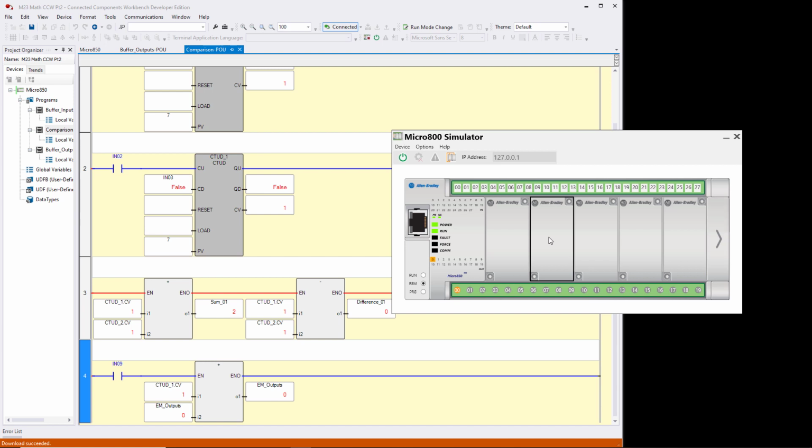But watch what happens as fast as I can turn it on and off. As fast as I could click it, it incremented to 291. So that means 291 program scans passed between when I clicked input 9 on and when I turned it off. So I'm going to double click it really fast. I'm not going to wait for it to turn on so that I can see it light up, just bang bang. Okay. Well, now we went up to 465. That's because I didn't zero it.